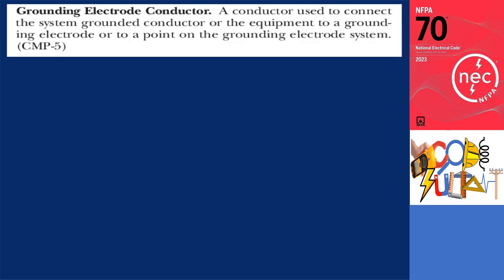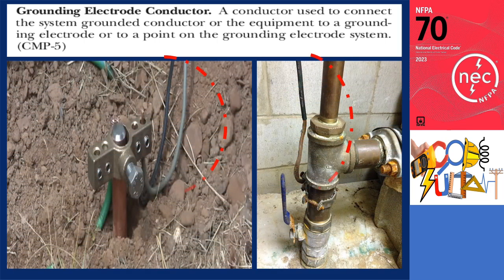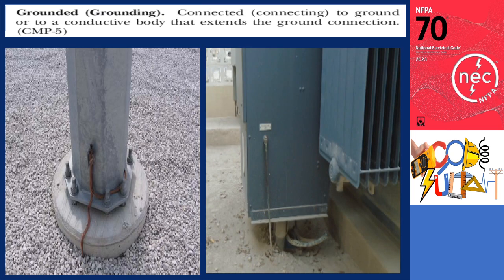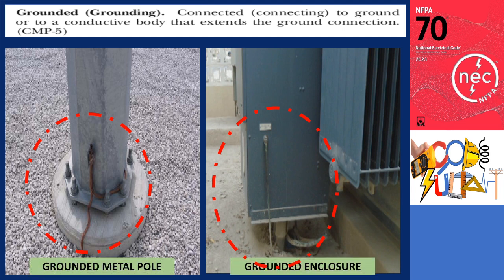A grounding electrode conductor is a conductor used to connect the system grounded conductor or the equipment to a grounding electrode or a point on the grounding electrode system. Grounded or grounding means connected to the ground or to a conductive body that extends the ground connection. Photos show an example of a body that extends the ground connection — the metal pole and the transformer enclosure are connected to the Earth either directly or by the termination to another grounding electrode.